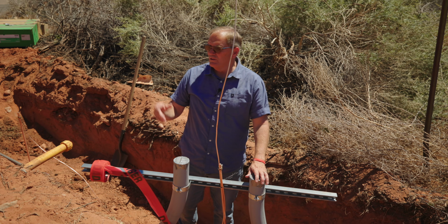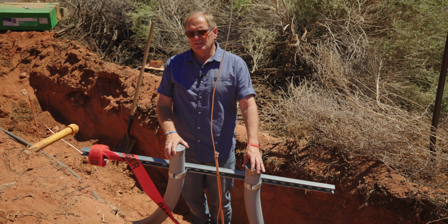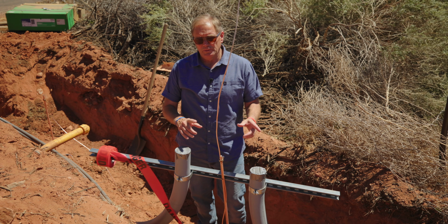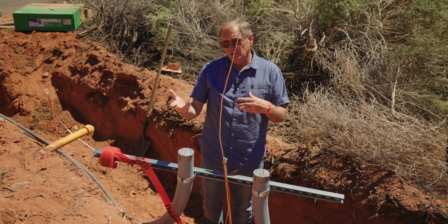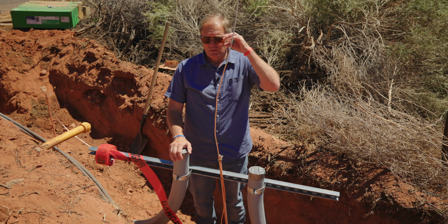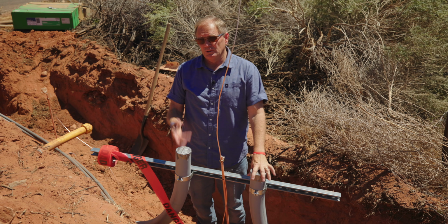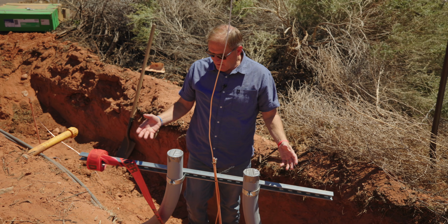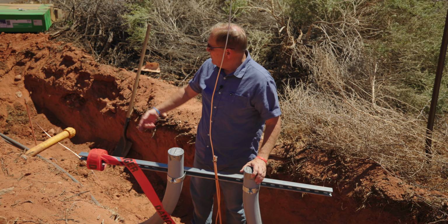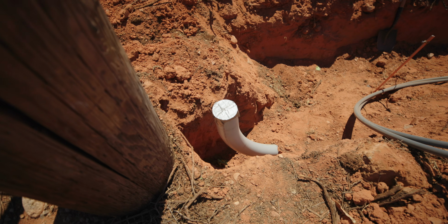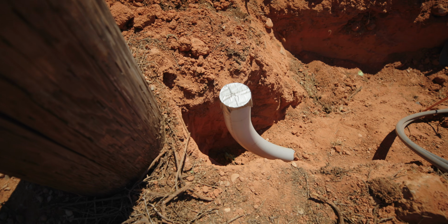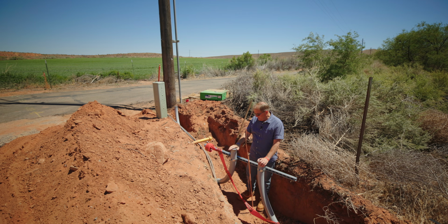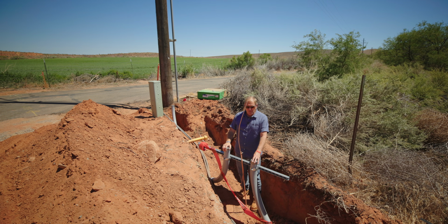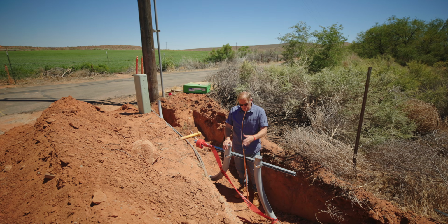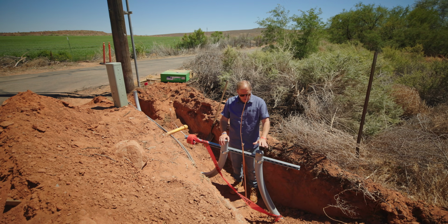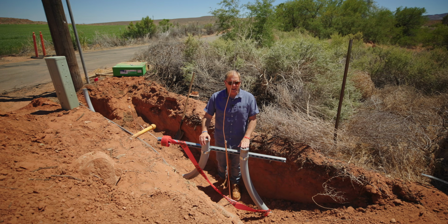Okay, here we are, near the pole. Again, a lot of communication has to take place between your power company, yourself, and even your client—if you're watching as a builder or as an owner builder, you are the client. We've got a conduit going up to the pole here, and they told us that needed to be 6 inches from the pole. Got that squared away. This is underground, had to be 3 feet down into the ground. That all passed. Got our grounding rod right here, and this is the supply to the house.